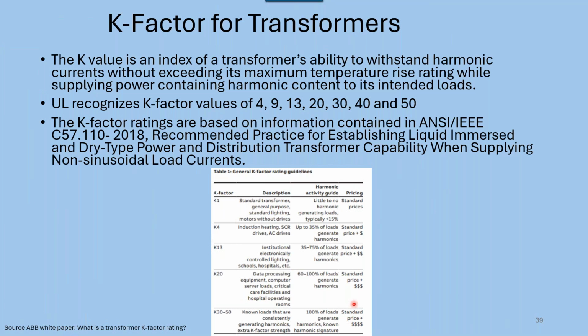So these are the different standards. For consulting engineers online, if you want to specify a K-factor, you could do that. And here's the standard. Don't specify K7 because it's technically not a standard. Okay. And these all fall under C57.110.